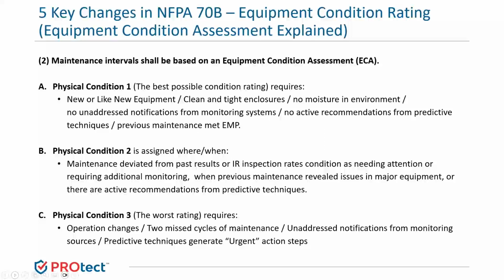And condition 3 is the lowest of the ratings. It's assigned where changes in operating conditions have been noted or when any of the following criteria apply. That could be the equipment has missed the last 2 successive maintenance cycles required by the electrical maintenance program. Both of the previous 2 maintenance cycles have revealed issues requiring repair or replacement of major equipment components. Or there are any unaddressed or active notifications from the continuous monitoring system or any predictive techniques that generate urgent action steps. That could be fault ratings from IR inspections or NETA fault ratings of 2 or 1, for example.